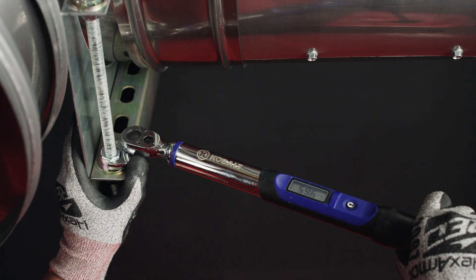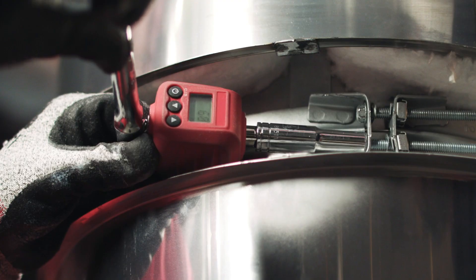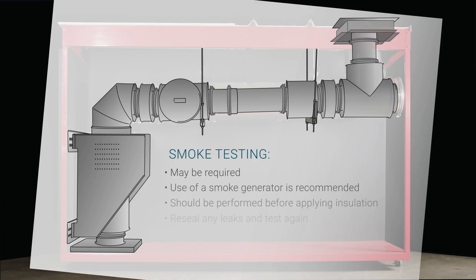You must also ensure that all hardware is tightened correctly. Some authorities having jurisdiction may require a smoke test to make sure all the joints in the duct system are leak-free. Do not use any smoke bombs that contain chlorinated chemicals. If a smoke test is required, we recommend the use of a smoke generator.